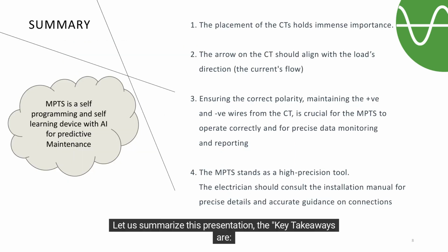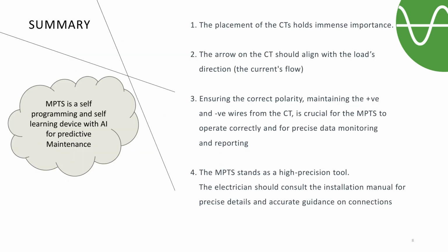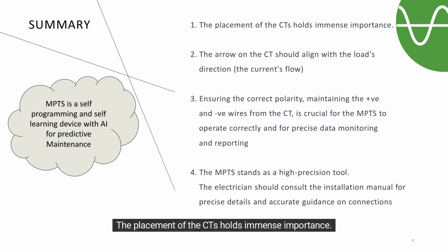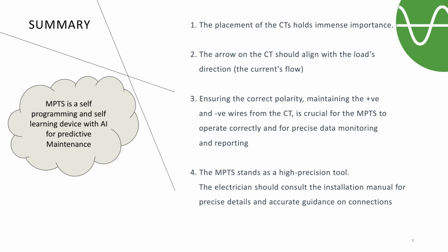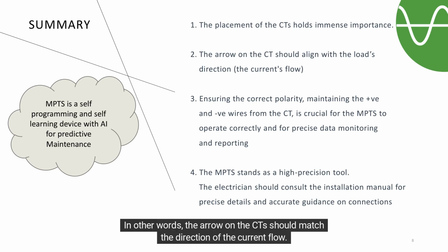Let us summarize this presentation. The key takeaways are: 1. The placement of the CT holds immense importance. 2. The arrow on the CT should point towards the load. In other words, the arrow on the CT should match the direction of the current flow.